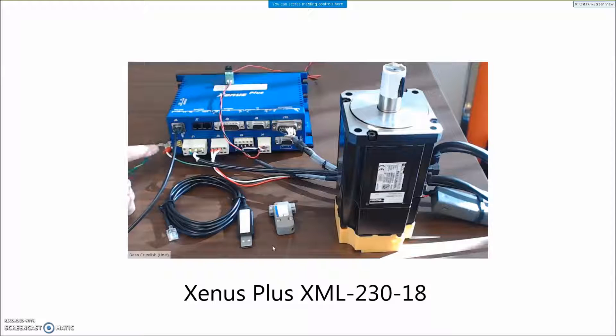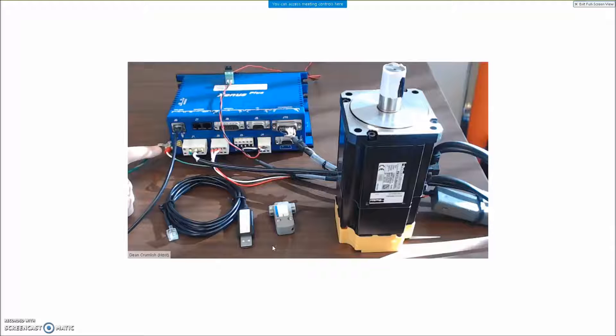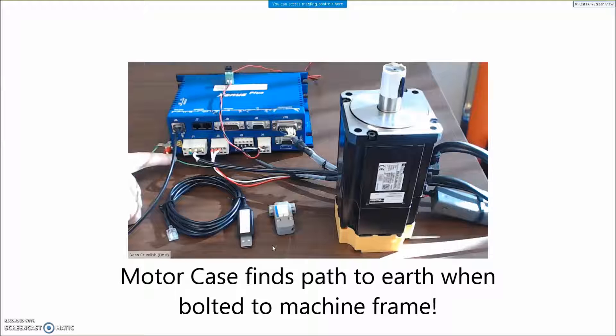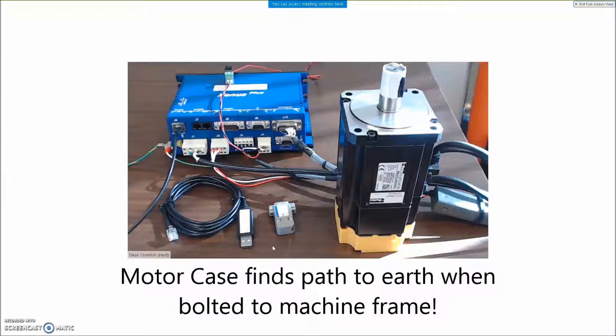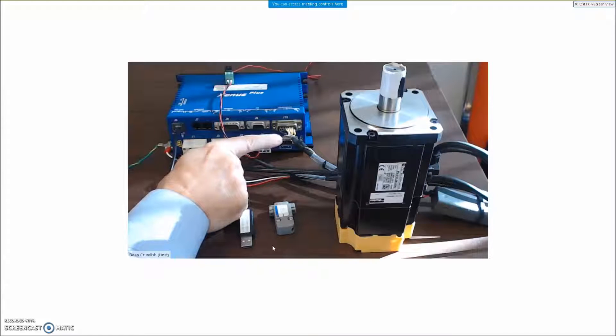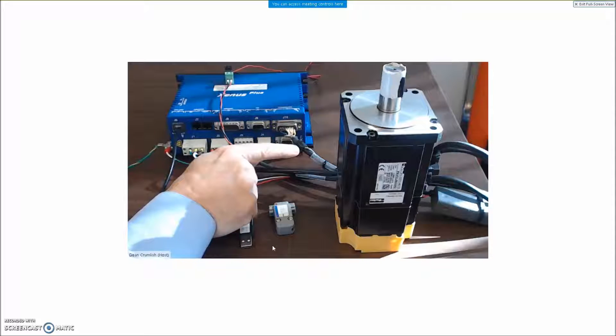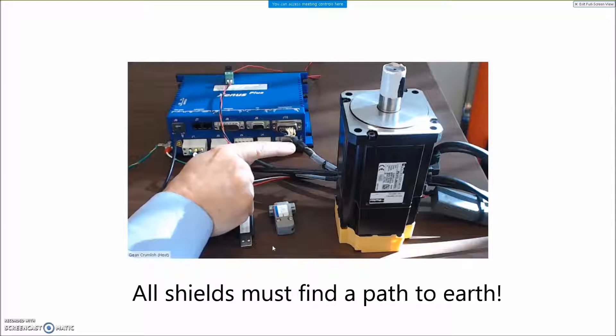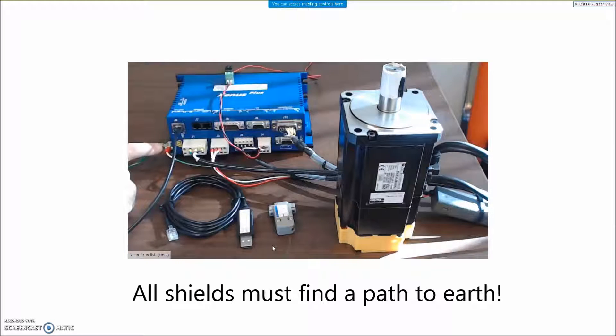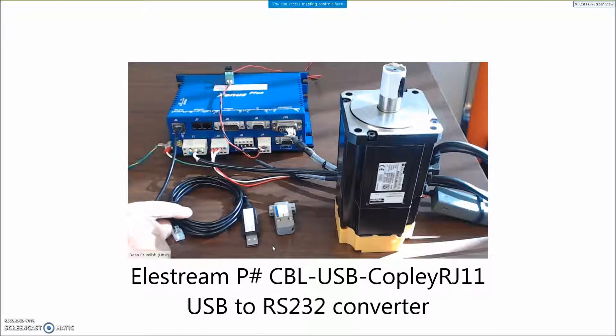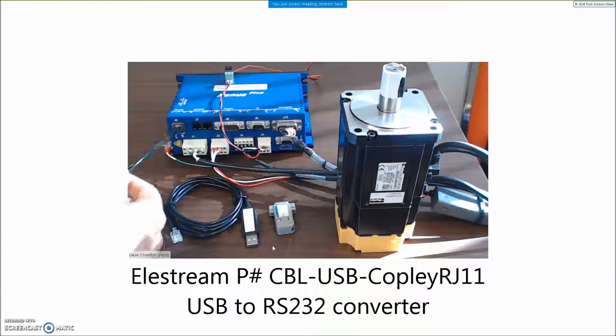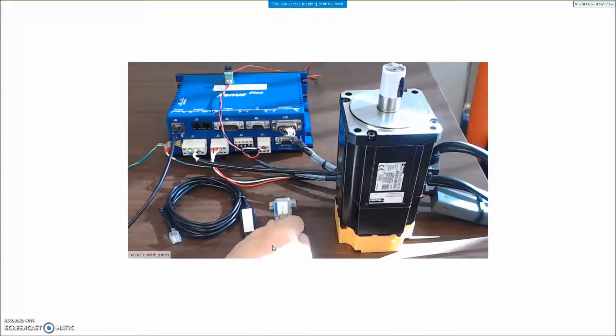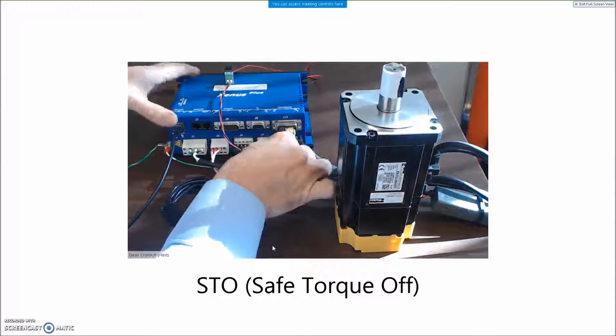Just wanted to show that we've got a ground terminal here to connect the earth so that we have good continuity to earth for the motor cable power wires and for the heat plate itself connected back to earth. On the feedback connector, it's very important that the shield be connected to pin 1 so that any noise picked up by the encoder, the electrons find a path to earth. I've also got this USB to serial RJ11 adapter for serial communication. This is a cool device and here's my STO jumper to bypass the safety circuit.